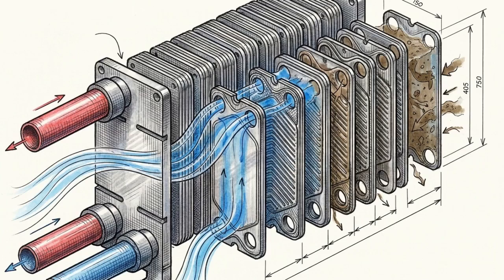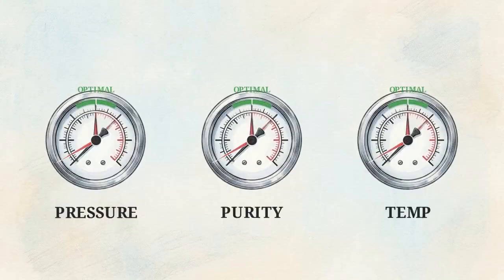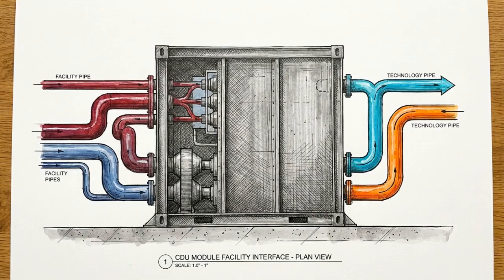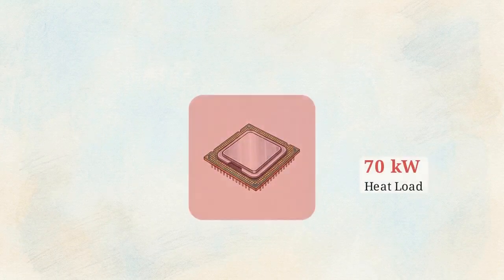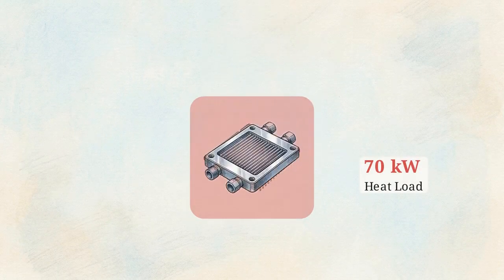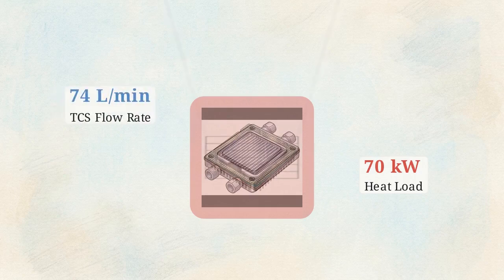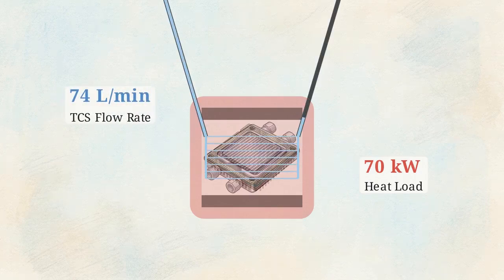These plates completely block exterior water chemistry, pressure excursions, and raw contaminants from reaching the data hall. The CDU is a control barrier. By mathematically regulating differential pressure, fluid purity, and approach temperatures, it isolates and protects the entire IT payload from external faults. Down at the server level, direct-to-chip cold plates pull heat off the processors. To remove 70 kilowatts of heat from a single rack, the system pushes a precise flow rate of 74 liters per minute across the server manifold.